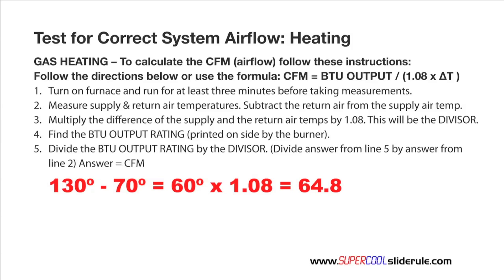The next thing we do is find the BTU output rating of the gas furnace. Be careful not to use the input — it must be the furnace output rating. We find this right here on the side of the furnace close to the gas valve. In this example, our output rating is 100,000 BTUs.